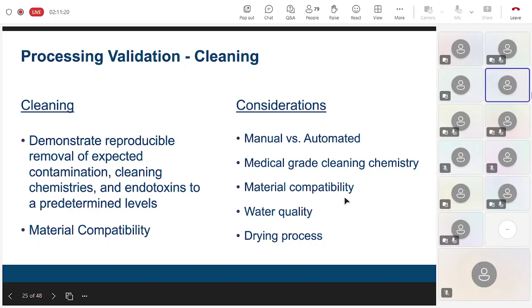We need to be very, very mindful of material compatibility, and that what we are washing is compatible with the material that we are using for the 3D printed device. We must be very, very careful of our water quality required for cleaning and rinsing of medical devices. Water impurities can have very bad effects on materials and can interfere with cleaning and sterilisation. So consider using utility water for intermediate rinses and critical water for final rinses.